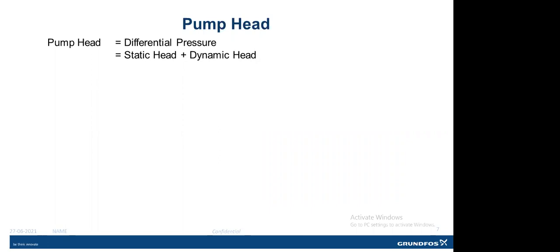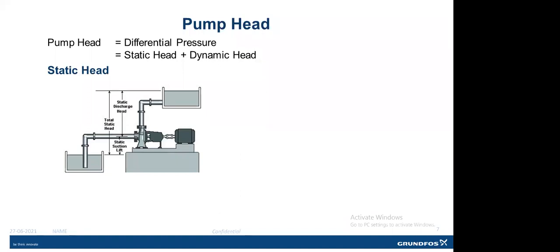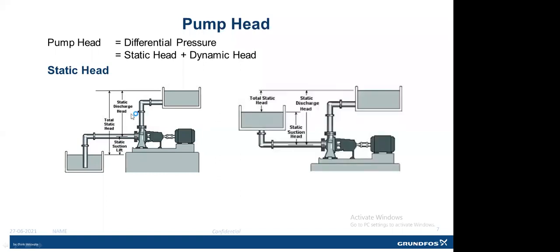And pump head. Pump head is nothing but the differential pressure across the pump, and it is the summation of static head as well as dynamic head. So we'll discuss static head and dynamic head. Static head is the height up to which the pump has to transfer the liquid. In this example, this is a negative suction case, and here the static head would be the difference between the two water levels, the summation of suction static lift plus discharge static head. This will be the total static head. And if we consider the positive suction head, the total static head would be the difference between the two water levels from the pump center line. So the total static head would be the discharge static head minus the suction static head. This will give us the total static head.